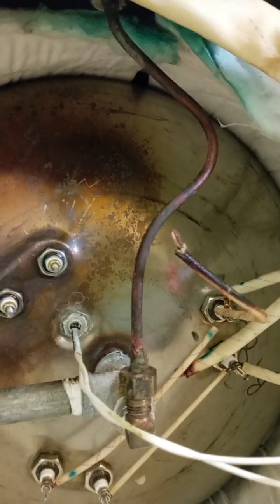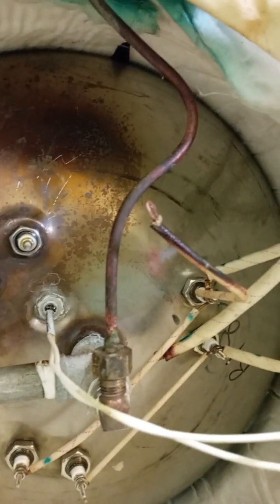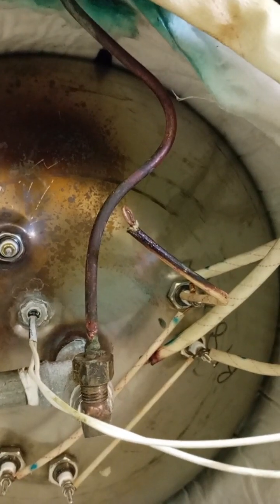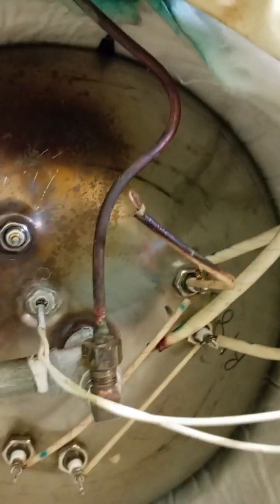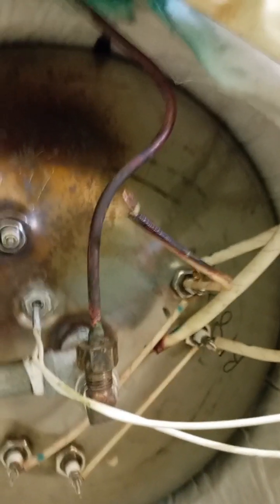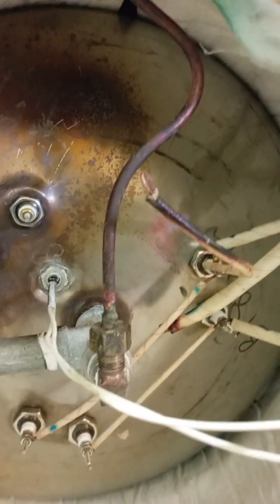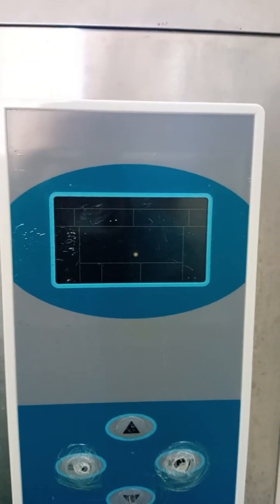So when this temperature reading fails, the autoclave cannot do anything, because the display will show some temperature errors, or sometimes you may boil for a long time but you will see the temperature not rising on the display. Let me show you the display of this. Do you see the display of the autoclave? The temperature readings will appear here, and also the time will appear here, and also when the sterilization cycle starts, you will see it on this display. Hey guys, can you see inside?